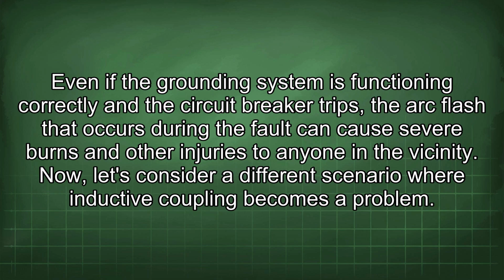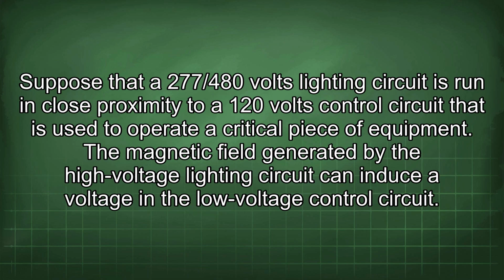Now let's consider a different scenario where inductive coupling becomes a problem. Suppose that a 277/480 volts lighting circuit is run in close proximity to a 120 volts control circuit that is used to operate a critical piece of equipment.